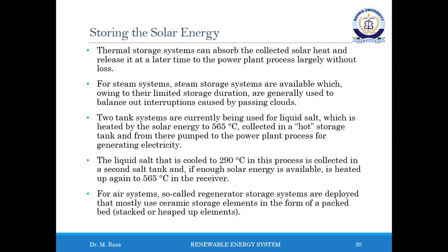For air systems, so-called regenerator storage systems are deployed that mostly use ceramic storage elements in the form of a packed bed. To charge a system, air flows through the packed bed from top to bottom, whereby the heat is transferred from the air to the storage medium. To discharge a system, air flows through the storage system in the opposite direction and is correspondingly heated up.